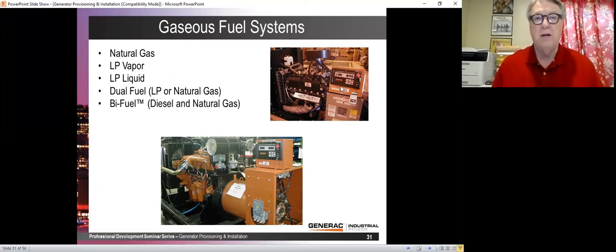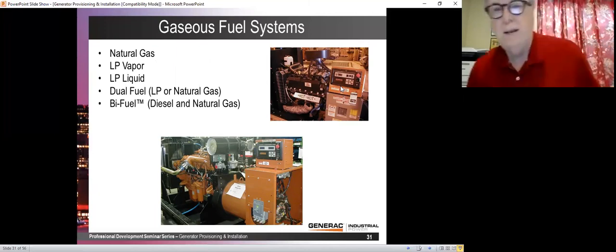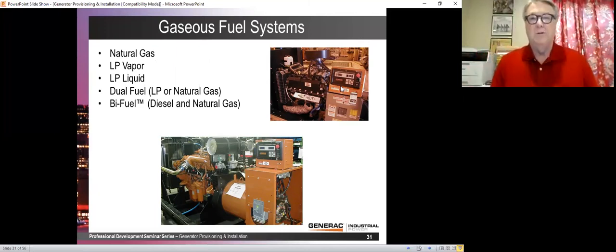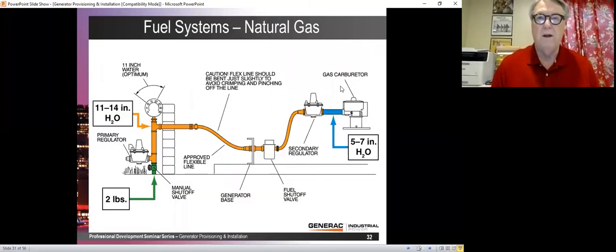Gas fuel systems, there's natural gas, LP vapor, LP liquid, that stands for liquefied petroleum, but typically we use propane. Then you have dual fuel, that is a natural gas generator that automatically switches to propane in the event that the natural gas system fails. Or we can have bifuel, that is a generator that runs on either 100% diesel or a combination of diesel and natural gas. Much cleaner, and we have those from the factory. Generac's the only manufacturer of those. Other people can retrofit them, third parties, but we have 500 and 600 kilowatt diesel generators that come from the factory as EPA certified bifuel.